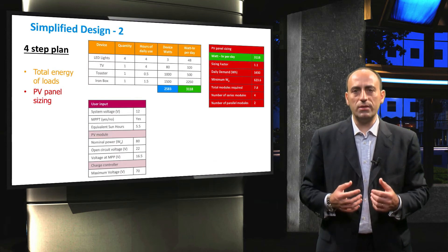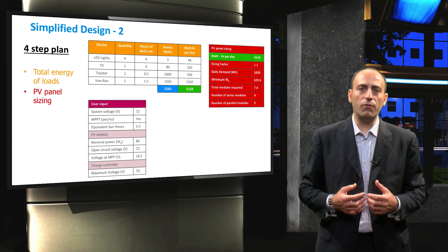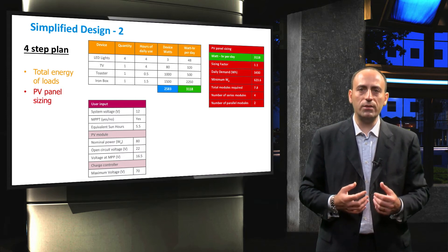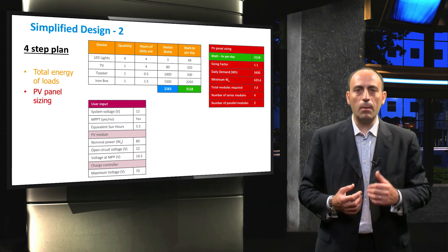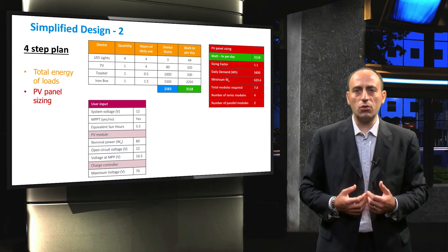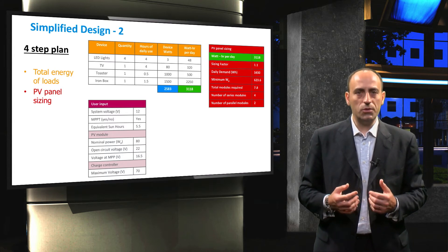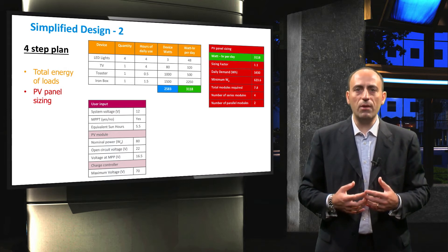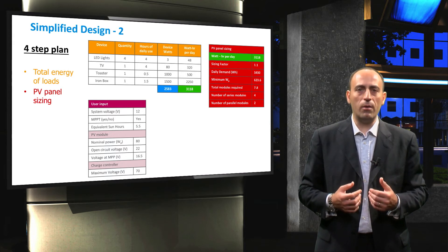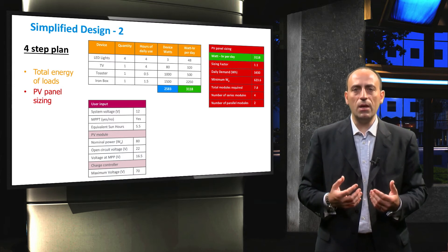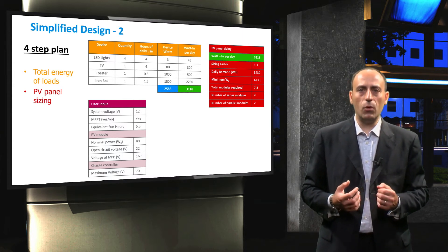To size the system, we first calculate the total number of required PV modules. This number is determined by dividing the above calculated minimum Watt-peak value by the nominal power of the PV module. We have also added the usage of a charge controller with an MPPT option. As you know, the MPPT decouples the load voltage from the PV array voltage, so that the PV array can be operated at its maximum power point voltage. Thus, the number of PV modules connected in series is calculated by dividing the maximum voltage of the charge controller by the MPP voltage of the PV module.